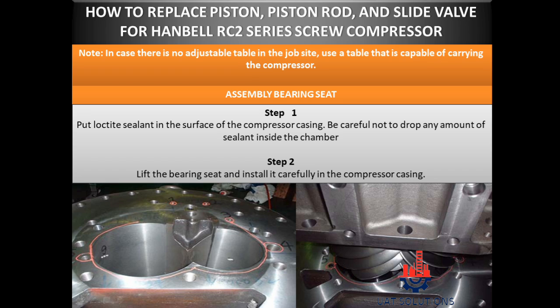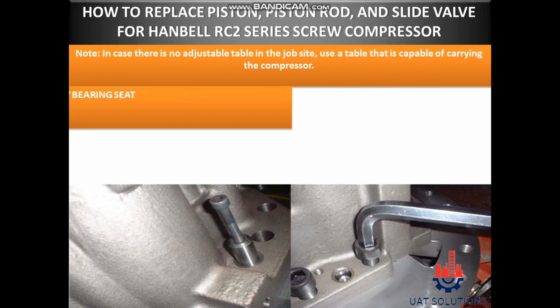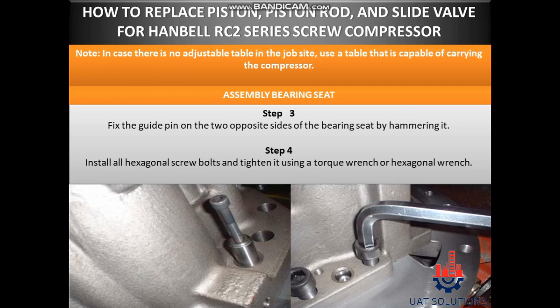Assembly bearing seat. Step 1: Put Loctite sealant on the surface of the compressor casing. Be careful not to drop any amount of sealant inside the chamber. Step 2: Lift the bearing seat and install it carefully in the compressor casing. Step 3: Fix the guide pin on the two opposite sides of the bearing seat by hammering it. Step 4: Install all hexagonal screw bolts and tighten using a torque wrench or hexagonal wrench.